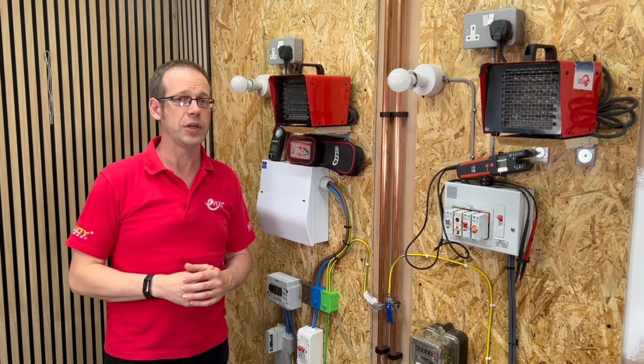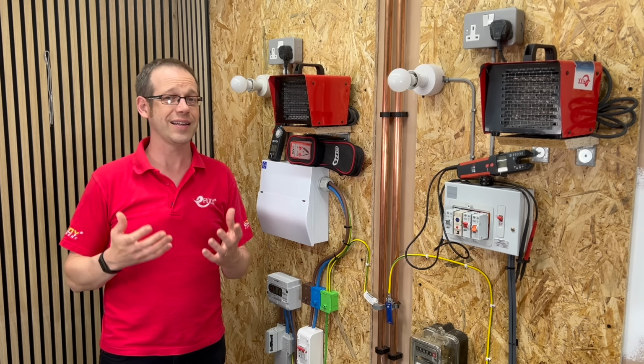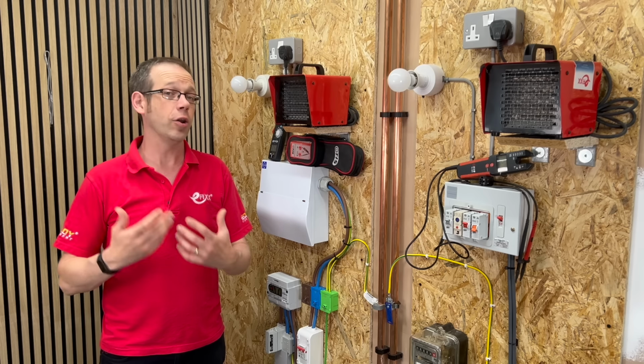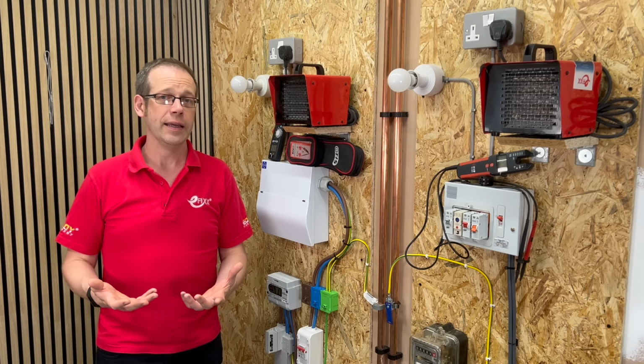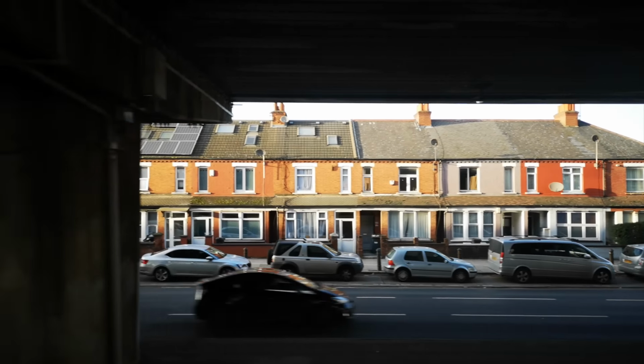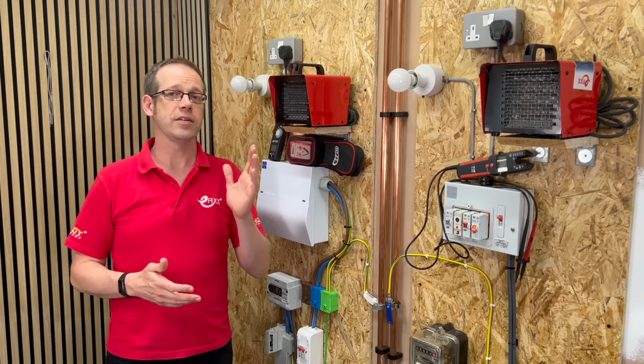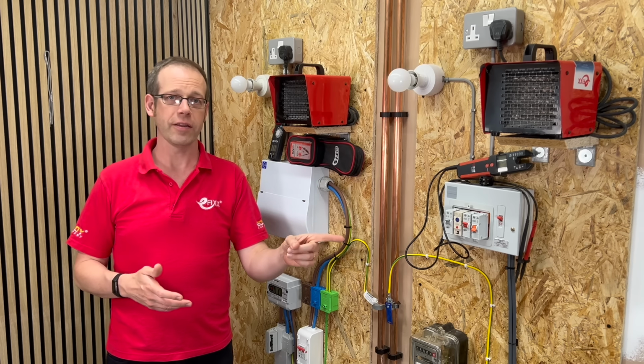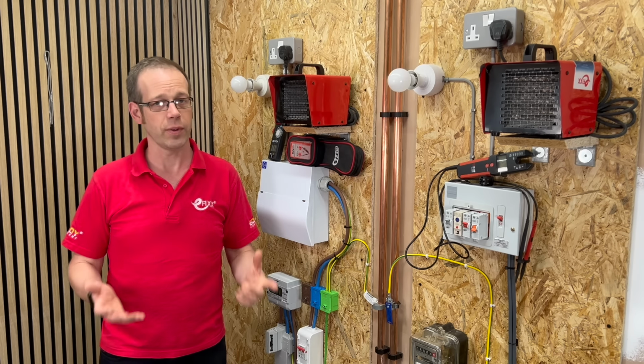Then you'd need to have a situation where the combined neutral and earth conductor has actually failed, followed by there being no other path back for the current to take. If multiple properties are tied to the metal incoming service, the current could well find its way back through one of those other connections. And if there's a sufficiently low earth path back to the transformer via the general mass of earth, this will help as well.